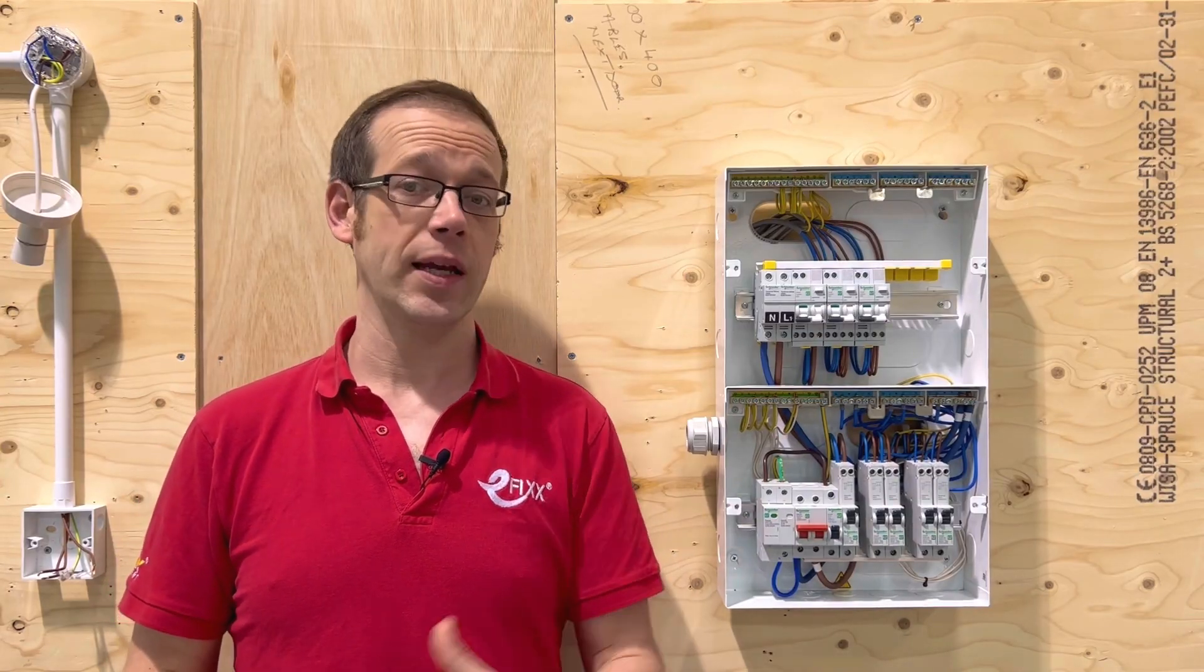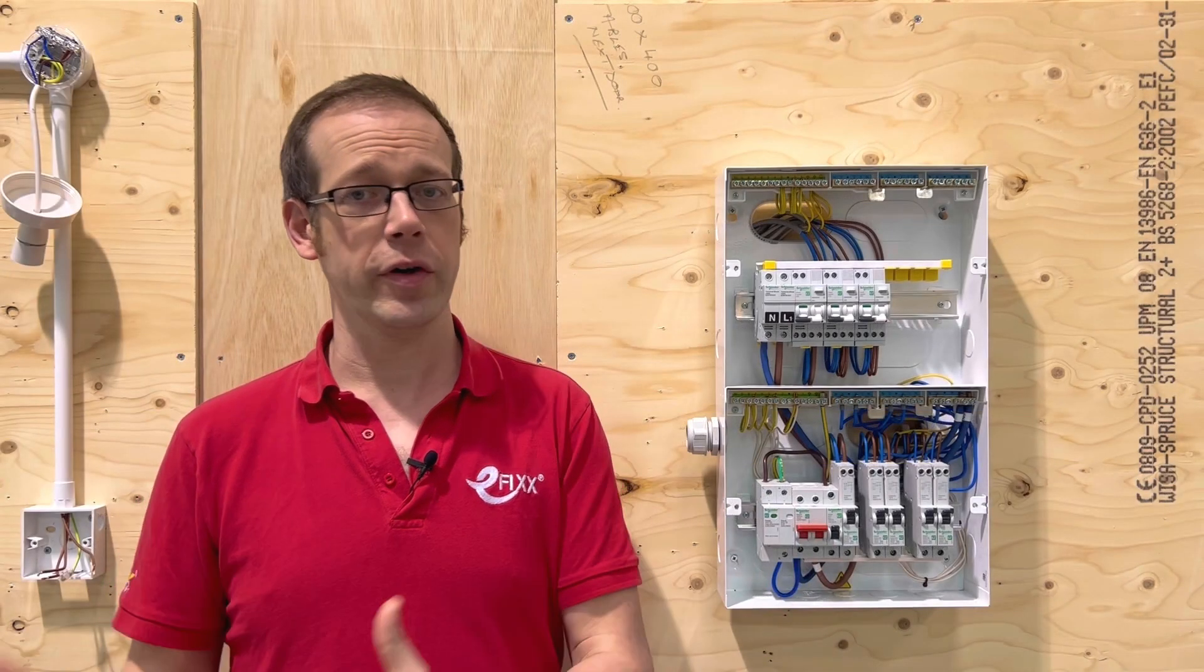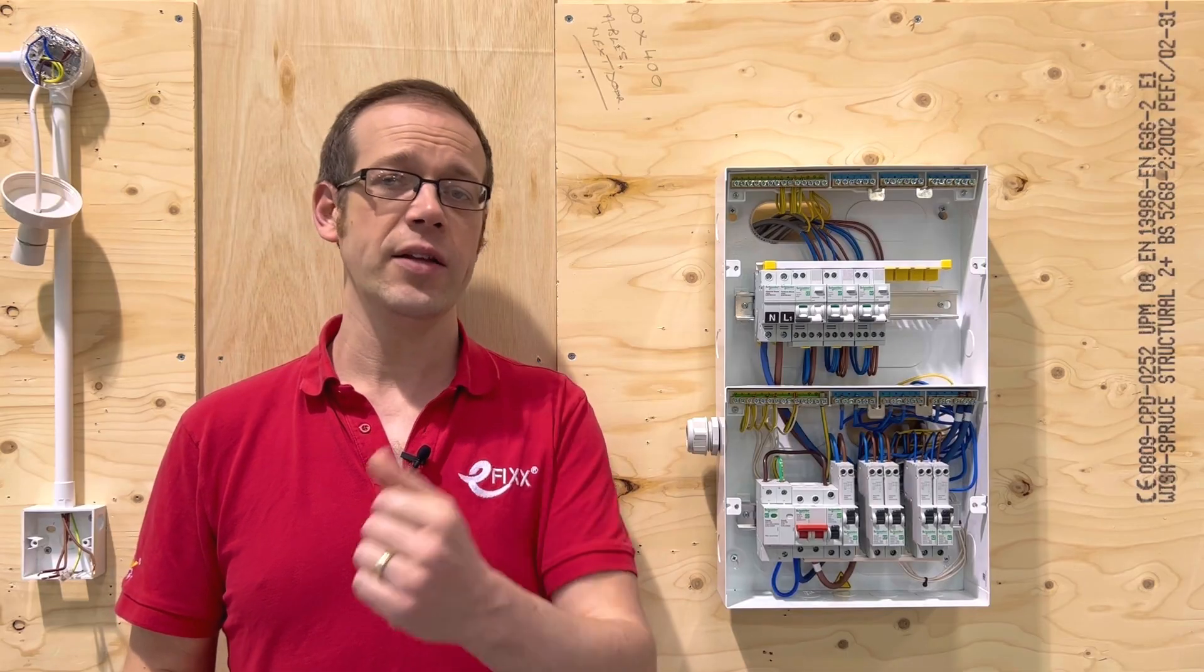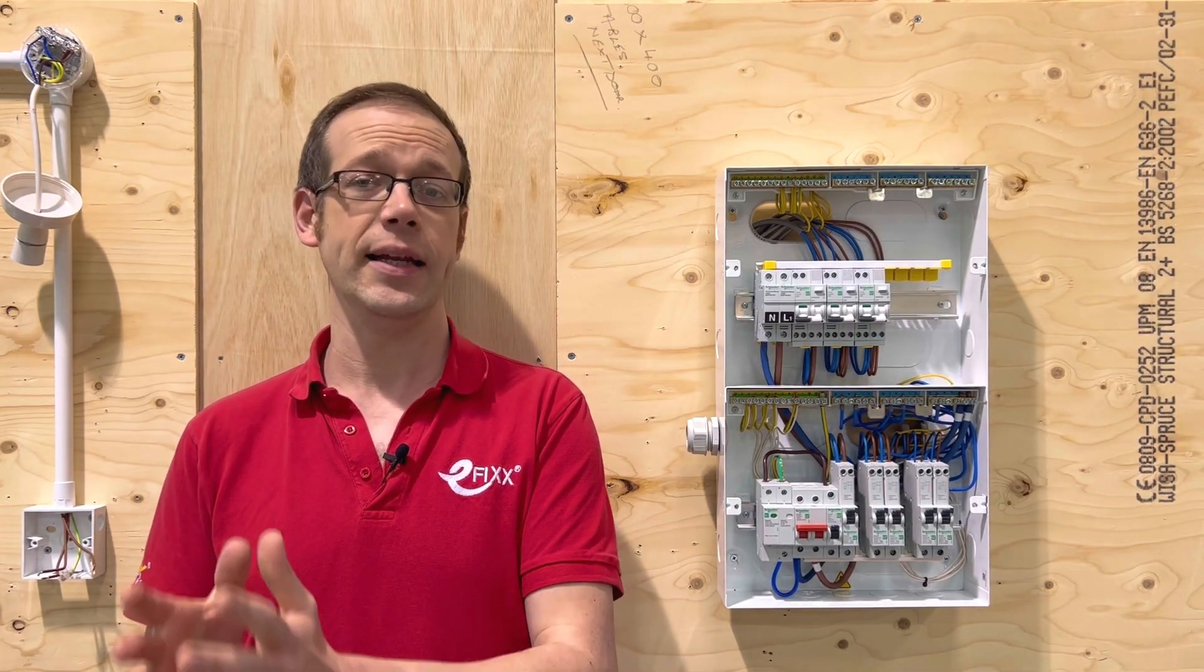This is then borne out in the next regulation 415.1.2 states that the use of RCDs is not recognized as a sole means of protection and does not obviate the need to apply one of the protective measures specified in sections 411 to 414. So we still need to use insulation, overcurrent protection and so on as well as using RCDs for additional protection. We can't just rely on the RCD alone.